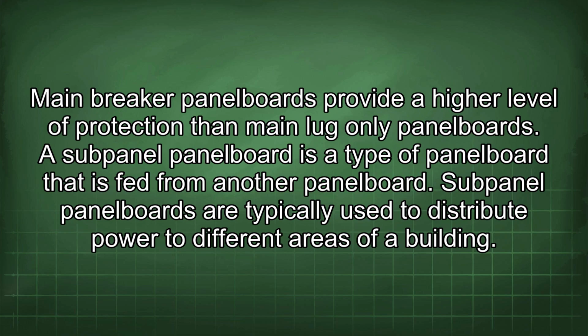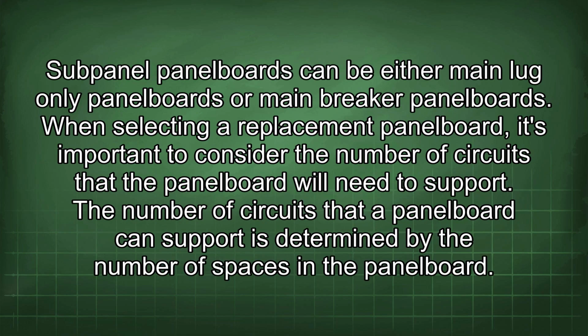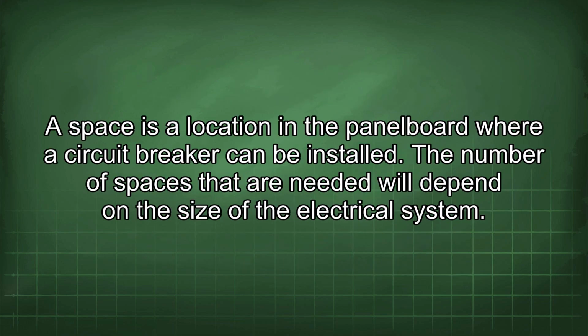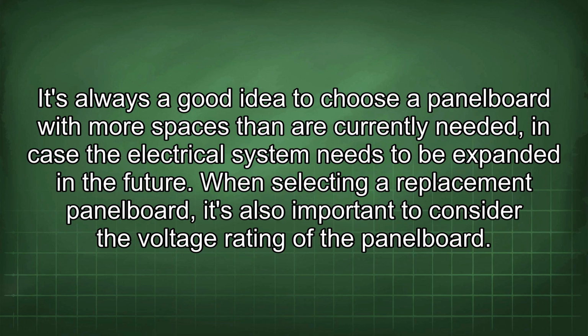A sub-panel board is a type of panel board that is fed from another panel board. Sub-panel boards are typically used to distribute power to different areas of a building. Sub-panel boards can be either main lug-only panel boards or main breaker panel boards. When selecting a replacement panel board, it's important to consider the number of circuits that the panel board will need to support. The number of circuits that a panel board can support is determined by the number of spaces in the panel board. A space is a location in the panel board where a circuit breaker can be installed. The number of spaces that are needed will depend on the size of the electrical system. It's always a good idea to choose a panel board with more spaces than are currently needed, in case the electrical system needs to be expanded in the future.